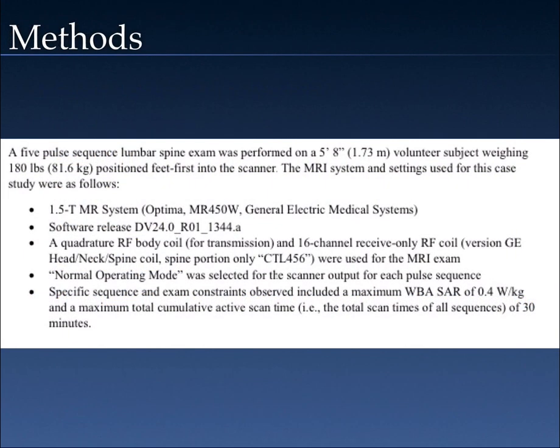The data was performed on a volunteer who was about 5 feet 8 inches and weighed around 180 pounds. They were positioned feet first into the scanner. It was a 1.5 Tesla GE Optima 450W system — a 70 centimeter bore using software release DV24. We used the integrated RF body coil for transmission and the 16 channel receive-only RF coil, which GE refers to as their head-neck-spine coil. We specifically selected the spine portion only, labeled CTL456 for the multi-coil configuration.